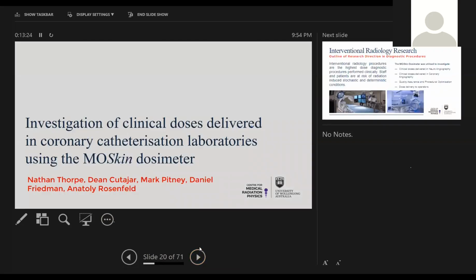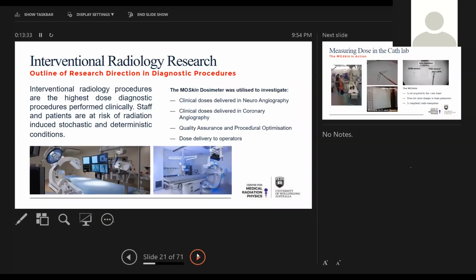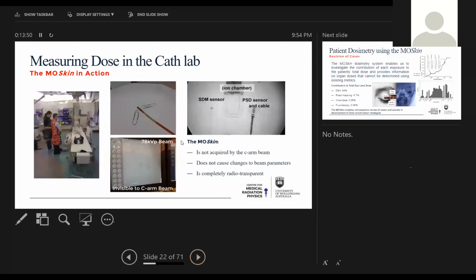Another interesting application, we're using these detectors in interventional radiology where doses can be quite high. So all of you are certainly familiar with the different procedures in interventional radiology, particularly neuroangiography, coronary angiography, and other applications. So what is the advantage of such a developed detector? The detector is invisible. You can see here 2 metal clips and the detector on the skin, but on the imager you can see only the clips. The detector you can't see, in comparison with other detectors, which always interfere with the field of view. And this we consider quite a big advantage that we achieved.